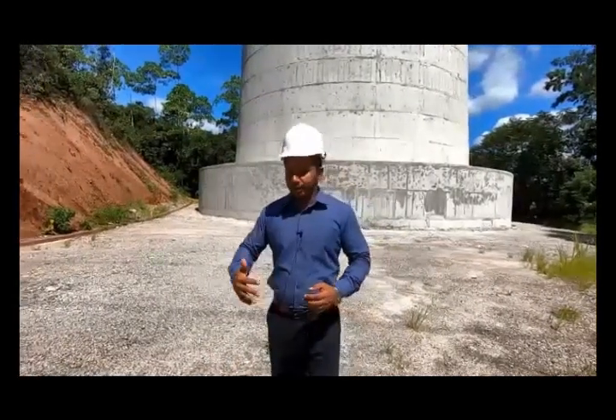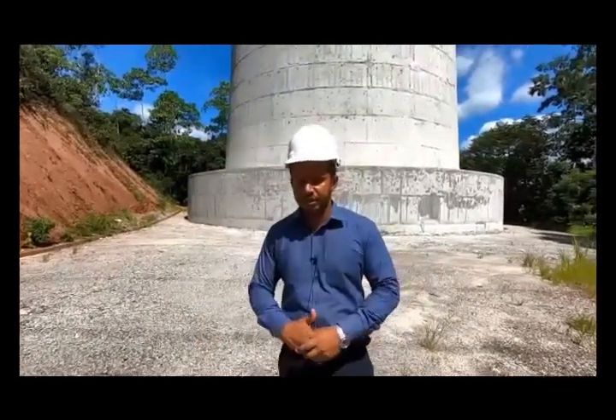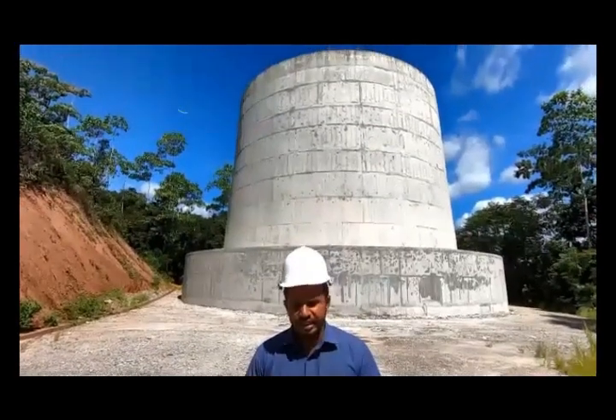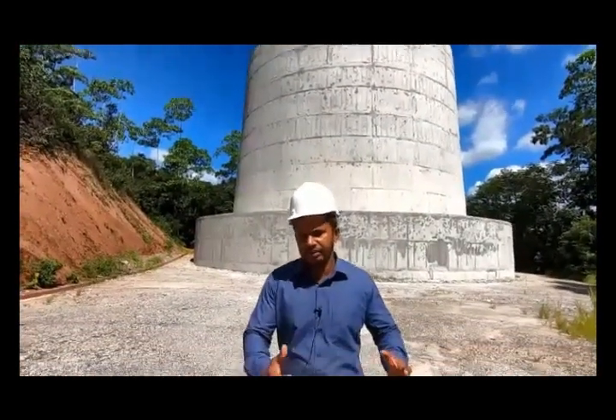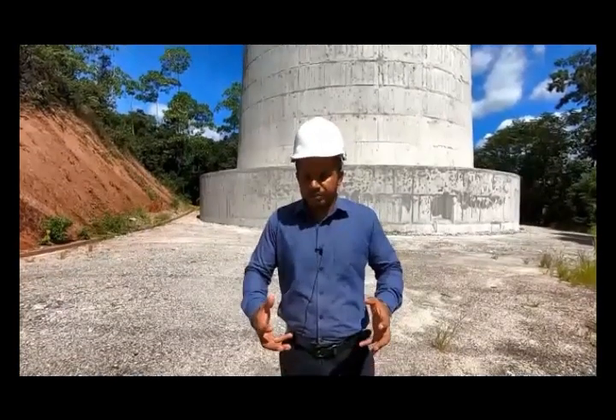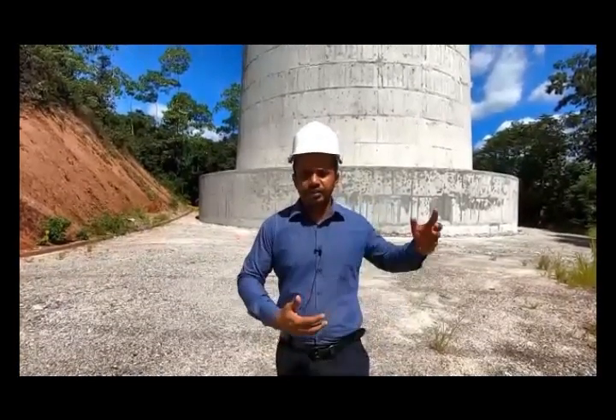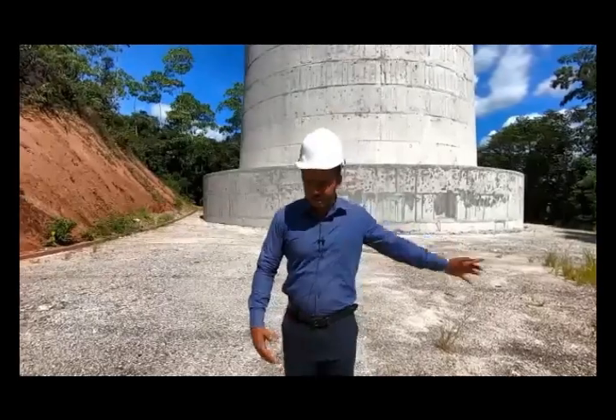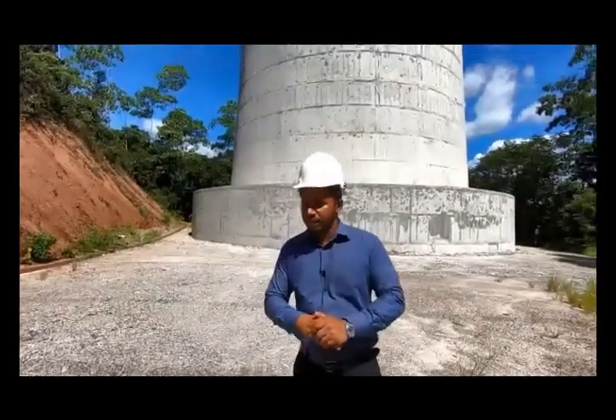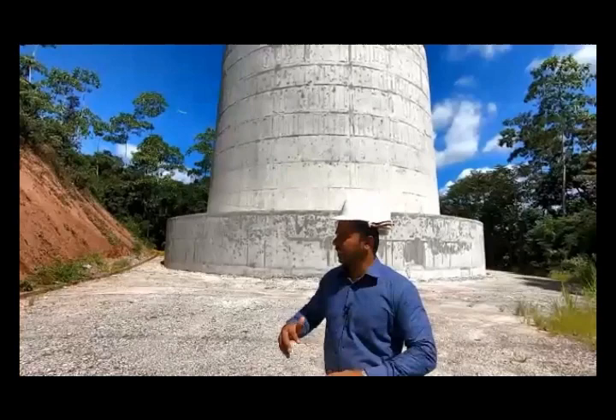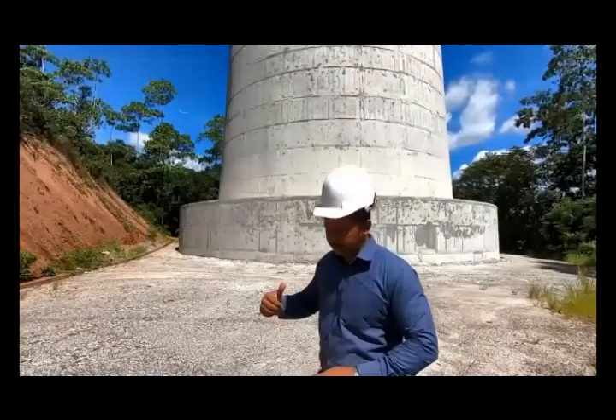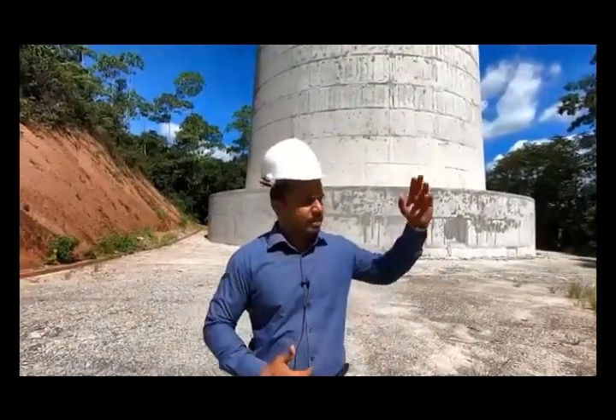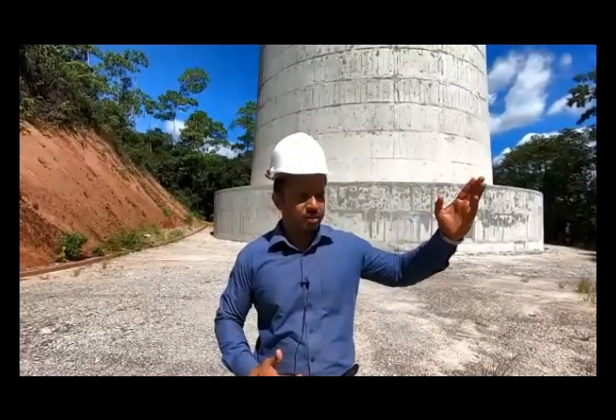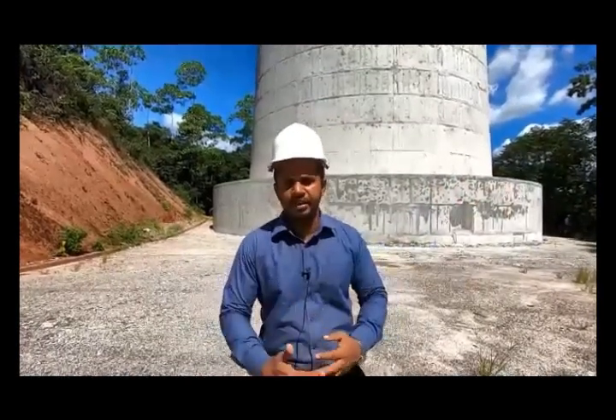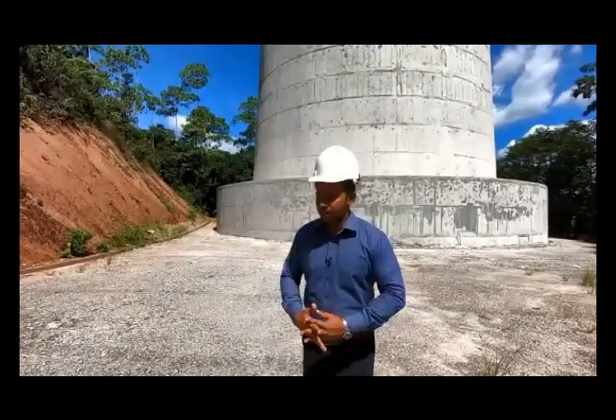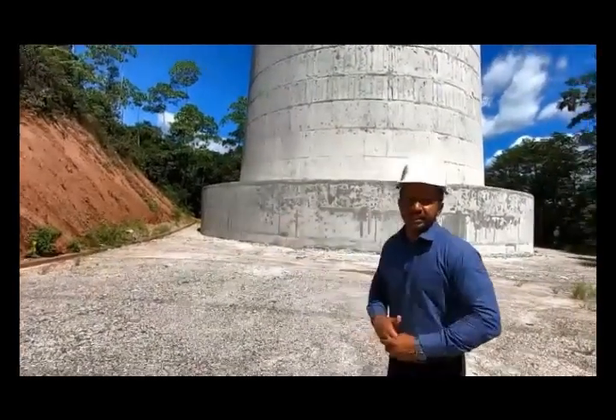Sometimes we need to close the powerhouse MIV valve suddenly, and then water hammer will occur on the penstock. We need to release that pressure somewhere, which is why we introduced this kind of surge chamber. This type of penstock surge chamber, the impedance type, was also introduced in other projects. If you follow me, we can go and see where we did this.